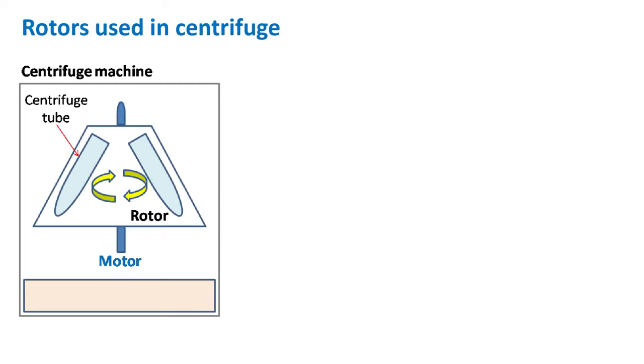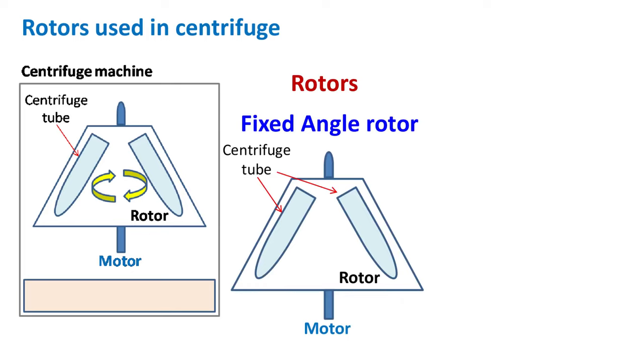Now let's talk about the rotors used in centrifuge. The rotors used in centrifuge are mostly of three types. First, fixed angle rotors. As the name suggests, these rotors will hold the tube at a fixed angle which is usually 45 degrees.